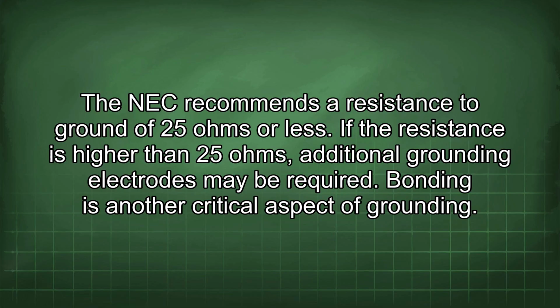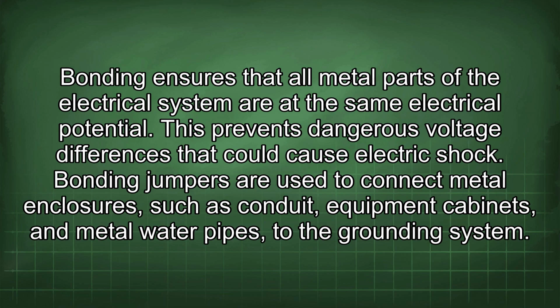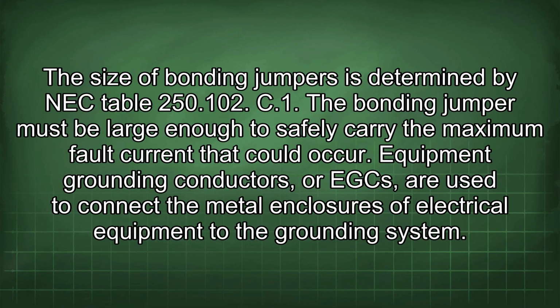Bonding is another critical aspect of grounding. Bonding ensures that all metal parts of the electrical system are at the same electrical potential. This prevents dangerous voltage differences that could cause electric shock. Bonding jumpers are used to connect metal enclosures, such as conduit, equipment cabinets, and metal water pipes, to the grounding system. The size of bonding jumpers is determined by NEC Table 250.102 C1. The bonding jumper must be large enough to safely carry the maximum fault current that could occur.